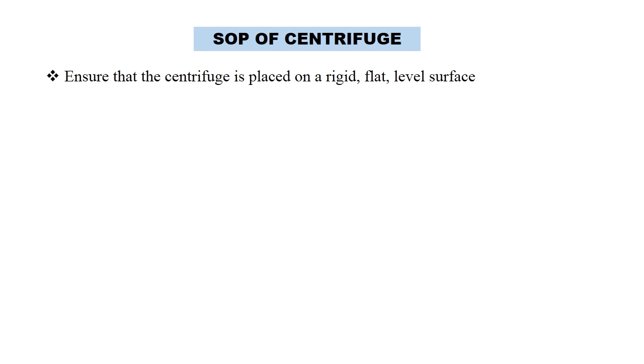Let us check the SOP of centrifuge. SOP stands for Standard Operating Procedure. So what are the steps? Ensure that the centrifuge is placed on a rigid, flat, level surface. Open the lid of the centrifuge and insert samples into the rotor with proper balancing. What is balancing? Balancing is placing two samples diagonally opposite of each other, preferably having equal volume.